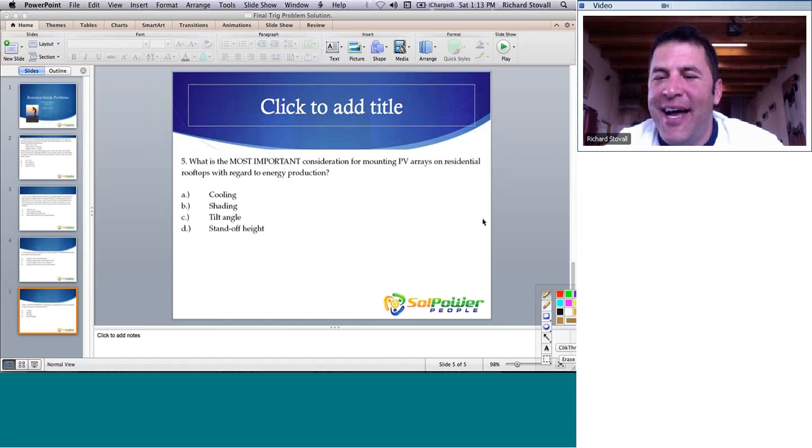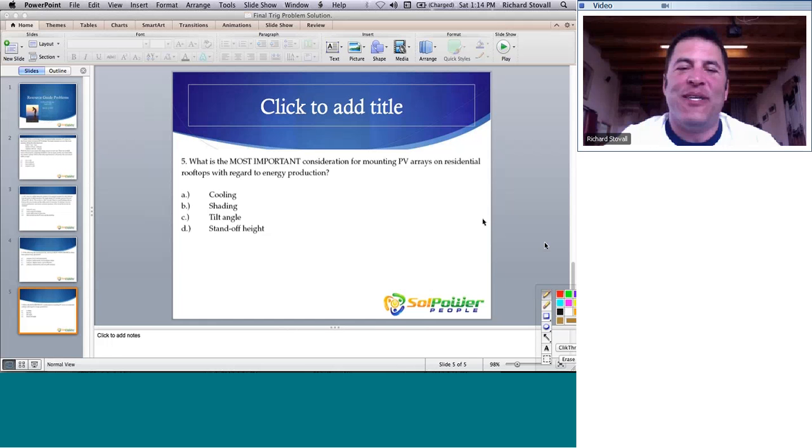Cool. All right. So Josh just put an answer in to question number five, I presume. By now you know that shading is probably the single biggest consideration for certainly a string inverter system, even microinverter systems. You really don't want shade, but the microinverter system or DC to DC conversion schemes will help mitigate shading, but you really don't want shading in a PV system, so that's the most important consideration.